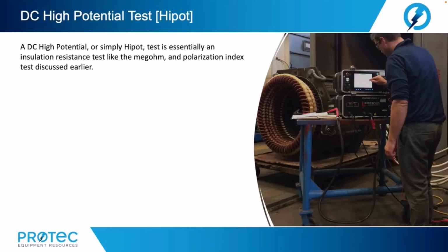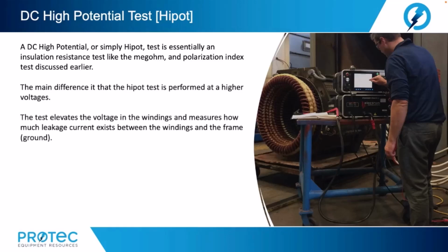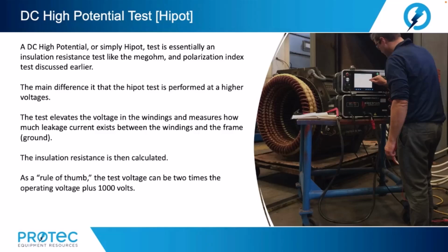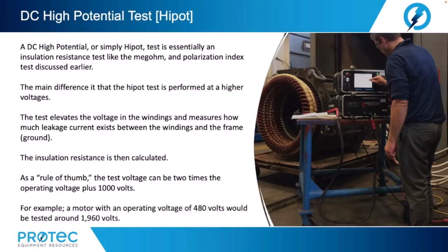All right, now let's move on to DC high potential or high pot tests. A DC high potential, or simply high pot test, is essentially an insulation resistance test like the megohm and polarization index test that we discussed earlier. The main difference is that the high pot test is performed at a higher voltage. The test elevates the voltage in the windings and measures how much leakage current exists between the windings and the frame, ground. The insulation resistance is then calculated. As a rule of thumb, the test voltage can be 2 times the operating voltage plus 1,000 volts. For example, a motor with an operating voltage of 480 volts would be tested around 1,960 volts.